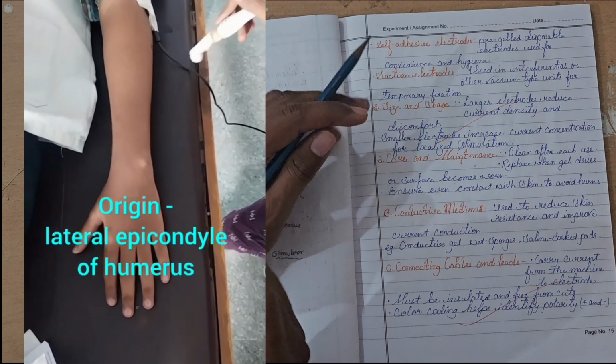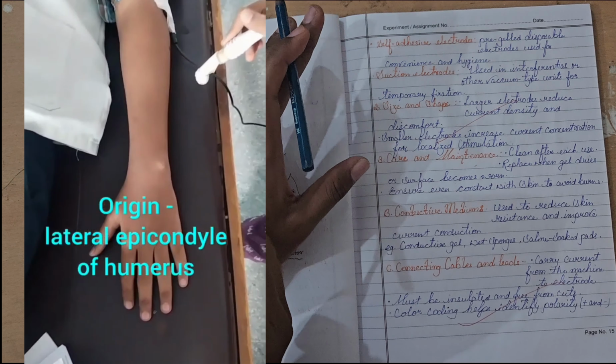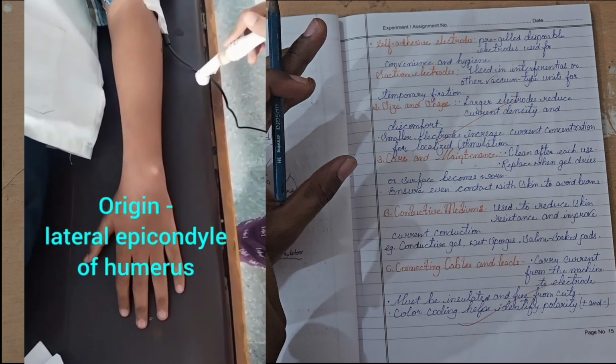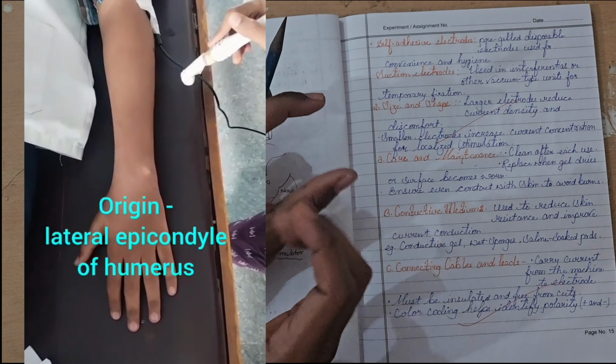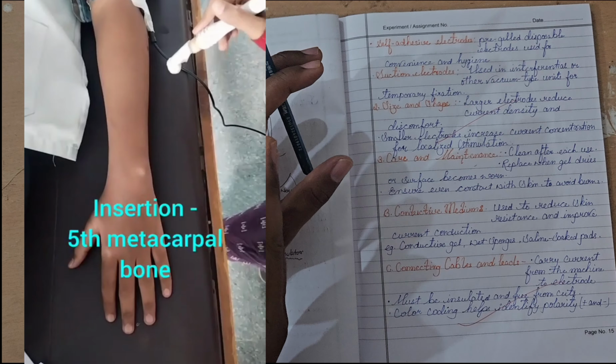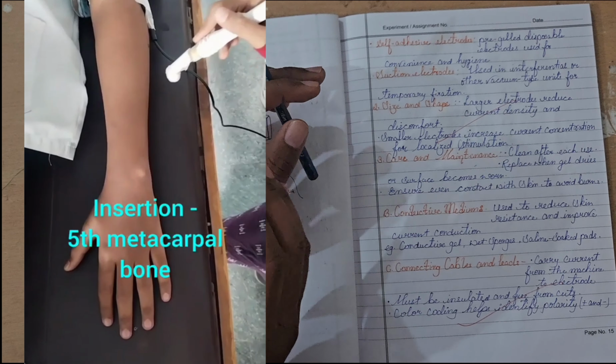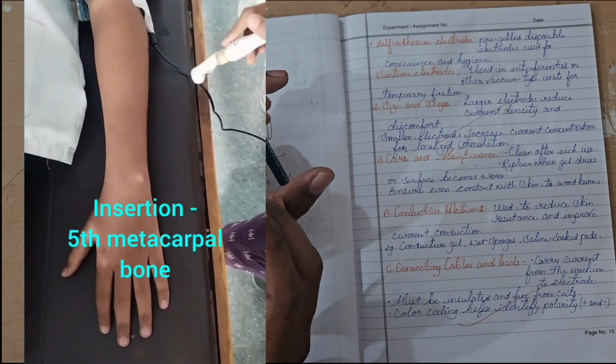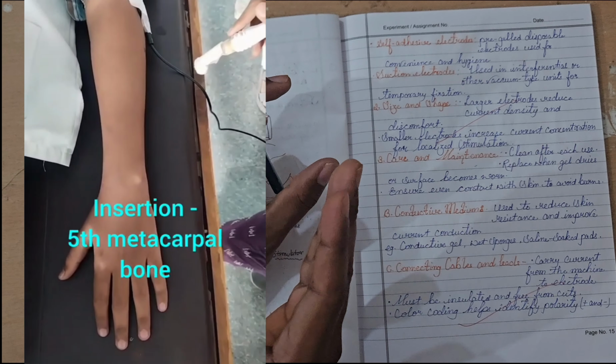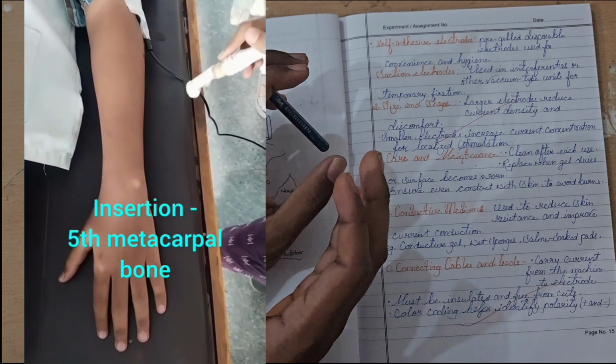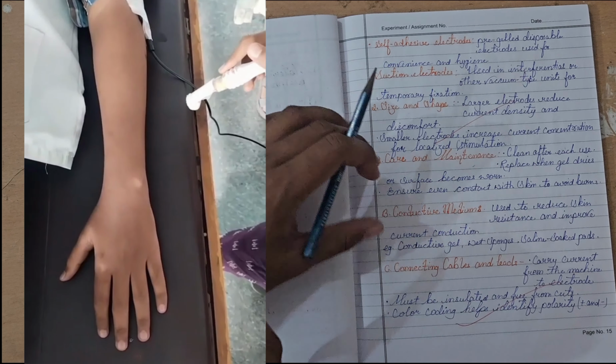Next one is the size and shape of the electrode. Large electrodes reduce current intensity and discomfort. Smaller electrodes increase current concentration and localized stimulation. If the pad is large, the current density is lower and discomfort is less. And if the electrode size is small, the current concentration is localized, and we can easily identify whether contraction or nerve stimulation is present or not.